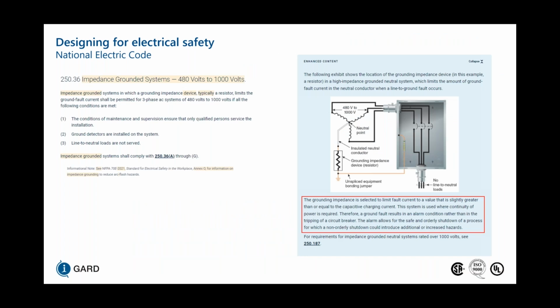Now, in the National Electrical Code, there's acceptance that impedance grounded systems can be used. It's noted that line-to-neutral loads cannot be served with a resistance grounded system because of the neutral voltage elevation that occurs during a ground fault scenario for high resistance grounding systems. So it says here that the grounding impedance is selected to limit fault current to a value that is slightly greater than or equal to the capacitive charging current. That way we can control those overvoltages.